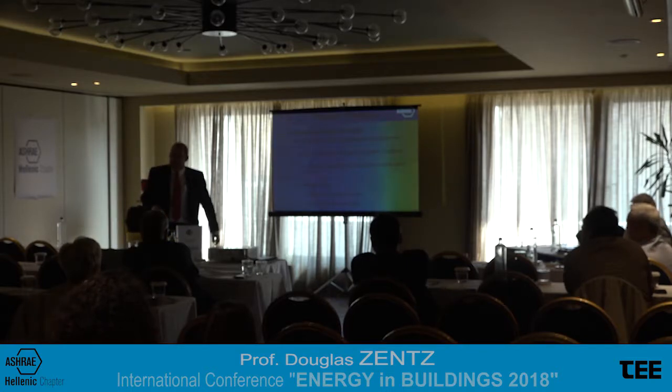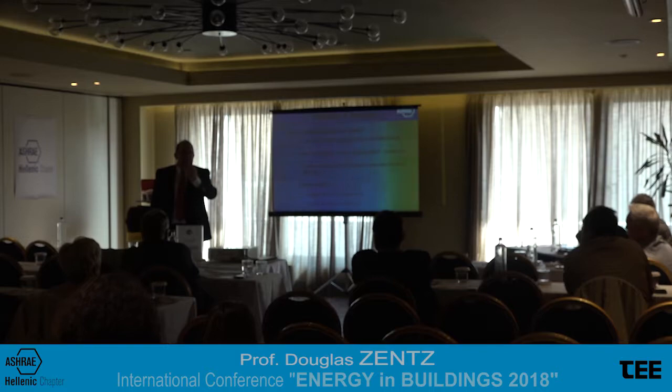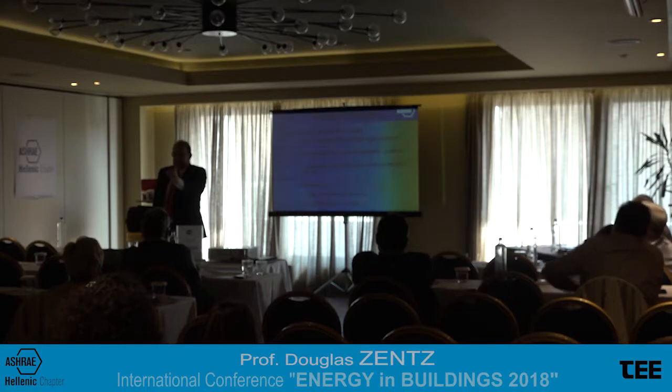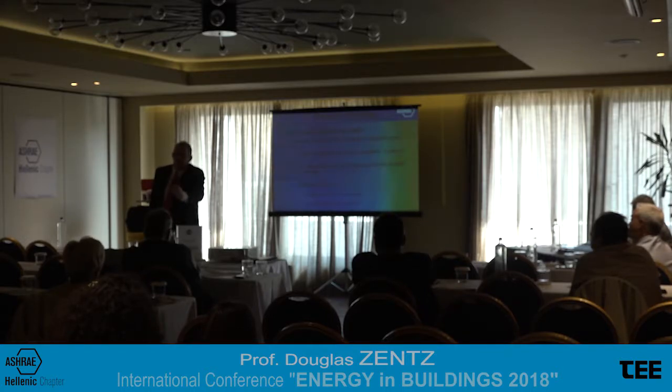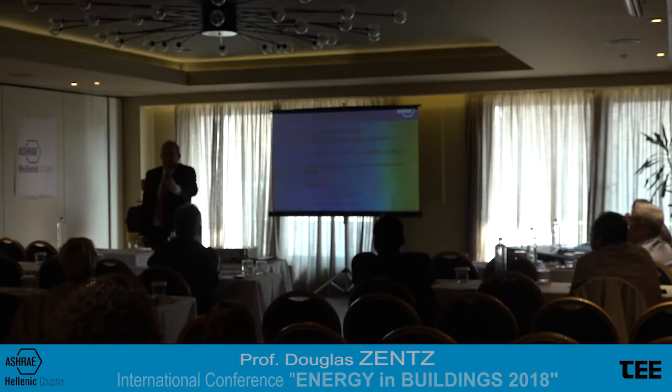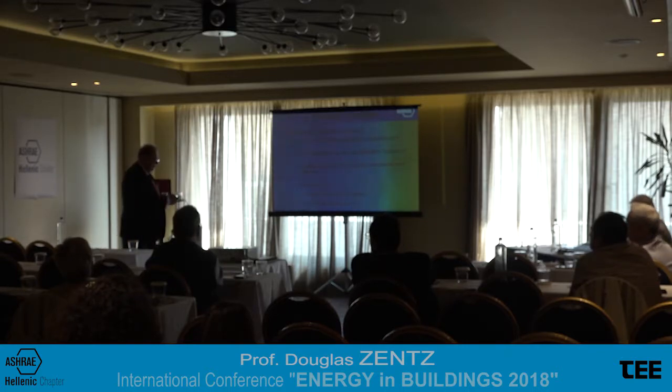But they also give you some nice things down here. They go beyond Standard 62 in giving you a lower baseline for people density factors, so you can actually get the demand controlled ventilation to work. You set the standard lower, and then you let the demand controlled ventilation work. So you're only using the minimum amount of air when there's really nobody there. So you lower the threshold and are able to actually use that demand controlled ventilation. Okay? So you get lower design assumptions, basically.